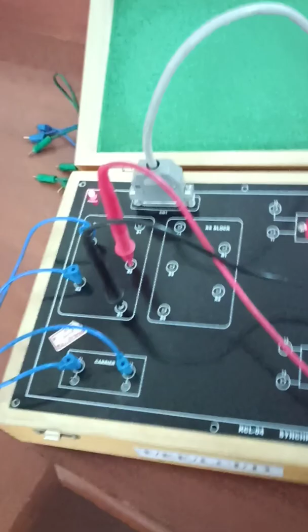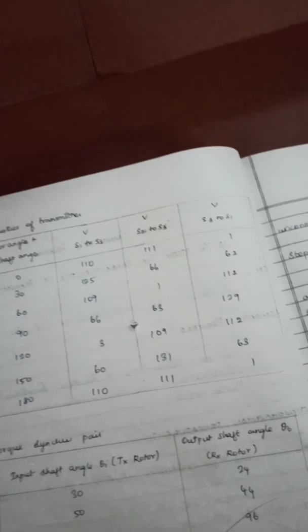Initially I'm going to set the shaft rotation to 0 degrees. Now it is at 0 degrees, and I'm going to measure the voltage between S2 and S3 as 68.8. I'm going to take this reading and note it here. For 0 degrees, S2 and S3, in the previous record it was a different value, but it can be any reading. Now I have taken the reading as 68.8.